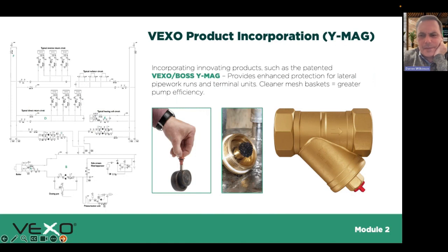Something we managed to get in here, and CIBSE let us have that in there, a bit cheeky, but something we've launched recently, Vexo, through BSS as a BOSS product, is an inline strainer with a dry pocket magnet. The idea is anything that would normally pass through the mesh, we can grab it, certainly anything attracted to a magnet, which in most cases is magnetite, covered in some form of biofilm and maybe some hard scale. The more we can do to prevent that strainer mesh from blocking, the greater efficiency on our pumps, less strain on them, and less maintenance. To be honest, how often do strainers actually get cleaned?